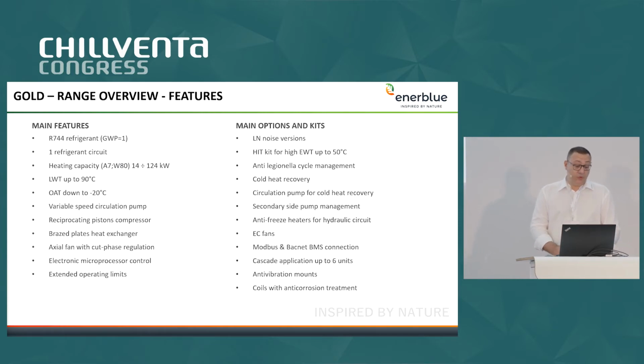Always an overview, we have the main features for the range. All the units have one refrigerant circuit. We already saw the characteristics for this unit. Compressors are piston reciprocating compressors. There is always a variable speed circulation pump installed. The heat exchanger is a brazed plate type, and we always have axial fans with cut phase regulation. Of course, the electronic control is included, and the working limits are very, very wide.